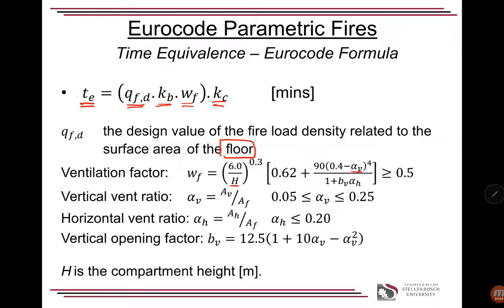Then we've got a ventilation factor which takes into account the height of the compartment and ventilation, and vertical and horizontal ventilation. And the vertical vent ratio, so that's the vertical vents, and it's just a ratio of the vent area to the total floor area. And then we've got a horizontal floor vent ratio, so that's roof ventilation. Just be careful though, because the Eurocode parametric fires actually state that the calculations we did in the previous example are not suitable for a horizontal roof vents. So you've got to be a little bit careful if you do a vent, because you're applying it to a parametric curve which is not suitable for roof vents. So just take cognizance of that.